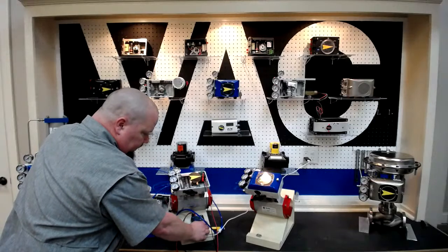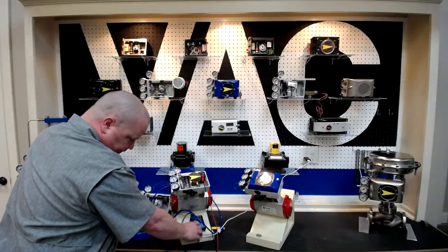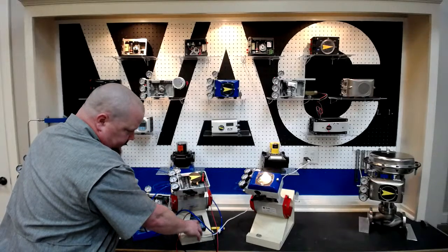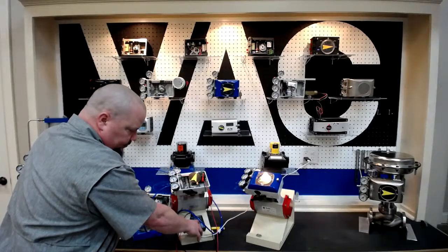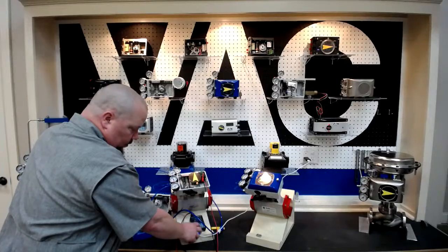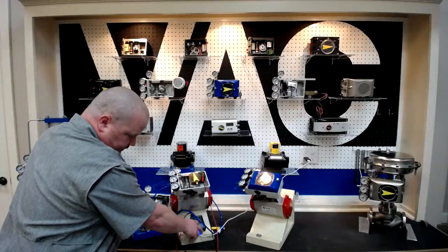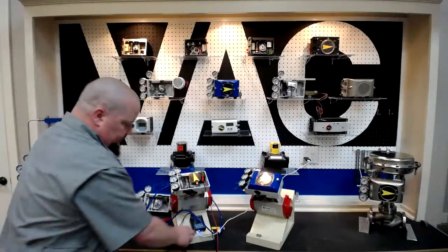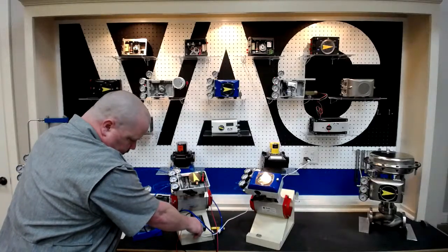I'm going to show this one more time so you can see what happens. So I'm going to show 4 milliamps, 5 milliamps, 6, up to 8. It jumps well over 50%. So now we're at 12 milliamps. We should be at 50%. We're almost 100%. And at 20, we go to full open.